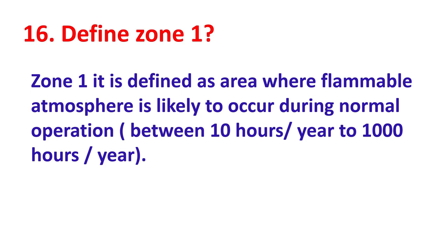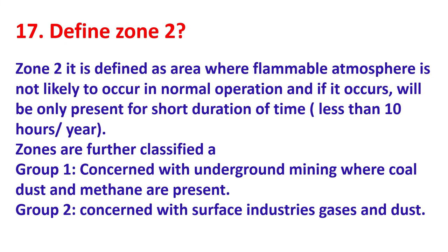Zone 1 is defined as an area where a flammable atmosphere is likely to occur during normal operation, between 10 hours per year and 1000 hours per year. Zone 2 is defined as an area where a flammable atmosphere is not likely to occur in normal operation, and if it does occur, it will be present only for a short duration of time — less than 10 hours per year.